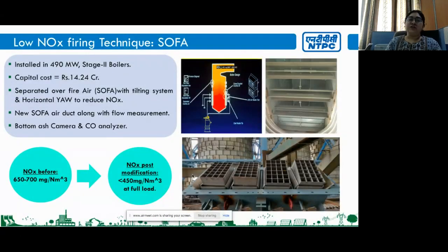For NOx reduction, in stage 2 of Dadri, we have installed separated overfired air dampers. Actually, the main purpose is to reduce the NOx levels. So what we are doing is that we are giving substoichiometric air in firing region, and the major portion, 20 to 25% of air, is being given through these separated overfired air dampers, resulting in decrease of NOx values. So we have installed one SOFA air duct with tilting system, horizontal yaw movement. We have installed bottom ash camera and CO analyzers to watch for flame instability. And we have been able to achieve NOx levels less than 450 milligram per normal meter cube. Earlier, it was 650 to 700 milligram per normal meter cube.